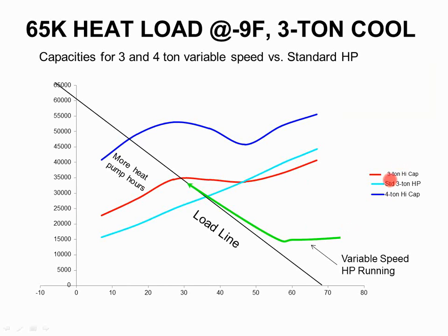Because on a mild day, you could always ramp it down. On a fixed speed piece of equipment or even a 2-stage piece of equipment, you can't do that. So do not upsize single and 2-stage heat pumps. If they're variable capacity, you can upsize them, basically one size. This is typically what we recommend on smaller heat pumps for upsizing, assuming you have the ductwork that can do the airflow. Right? So if you got a 2 or 2.5 ton, we say put a 3-ton in. If you got a 3-ton, we say put a 4. If you got a 3.5 or bigger, we say put the 5-ton in.